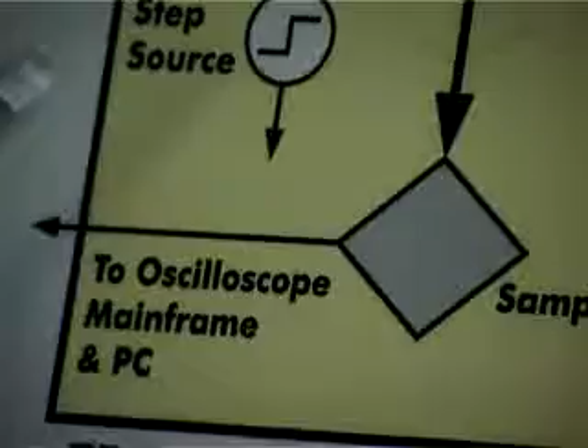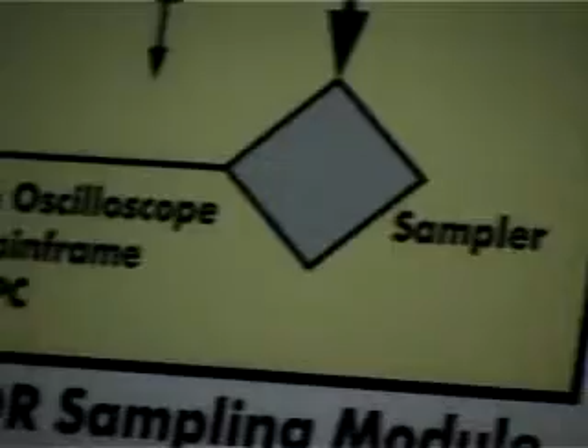This block consists of the step source generating a pulse which is sent to the moisture probe. After some time, the pulse returns from the moisture probe, and the time delay of the pulse is proportional to the material surrounding the probe, in case of moisture.